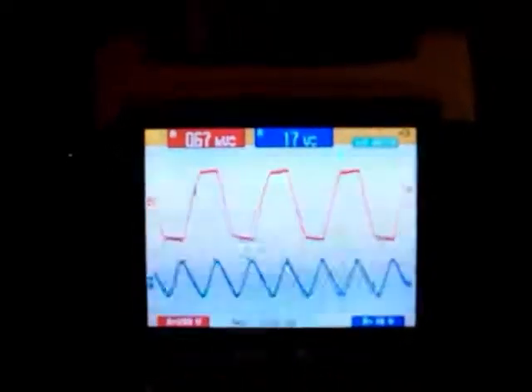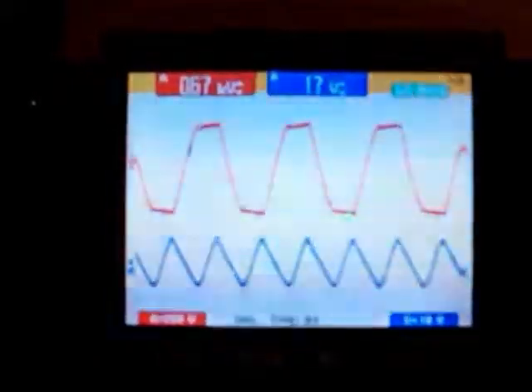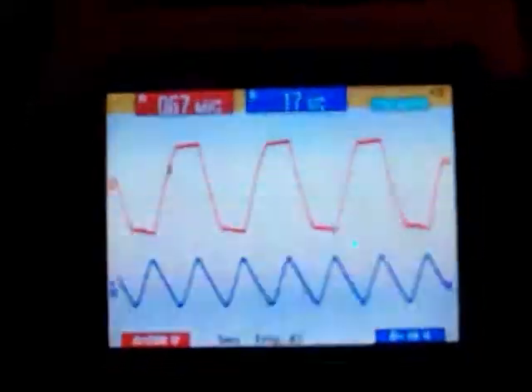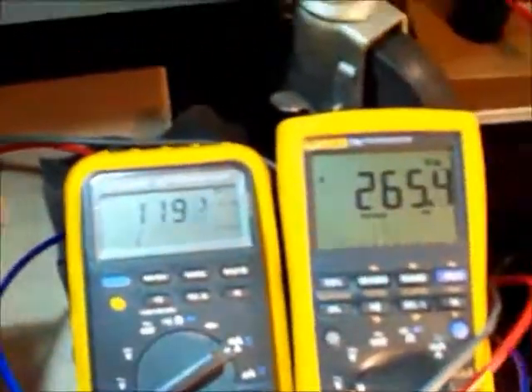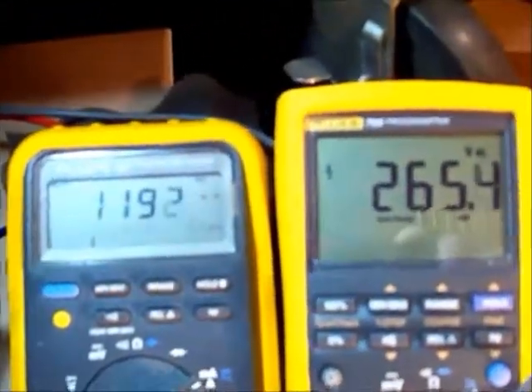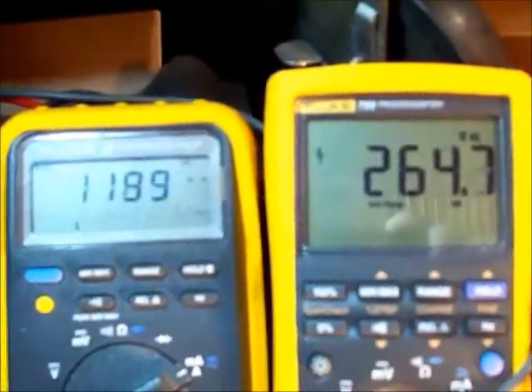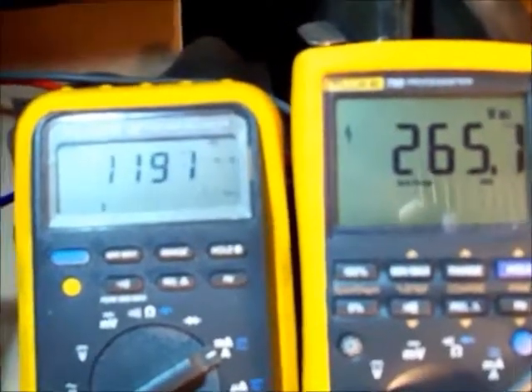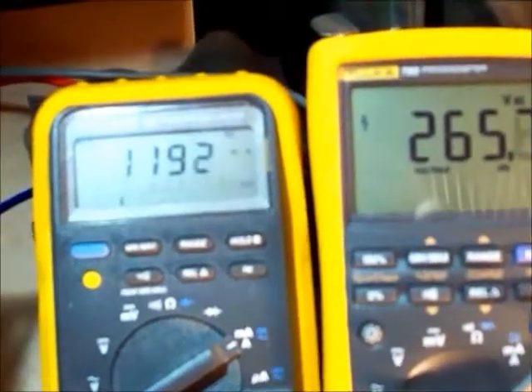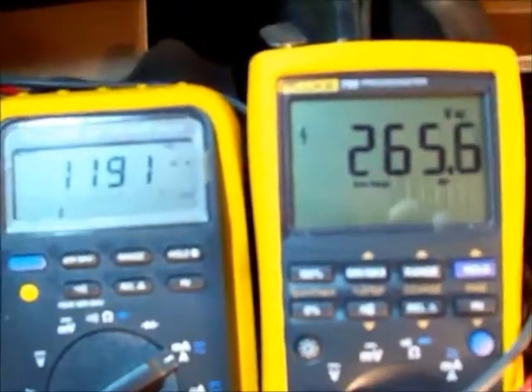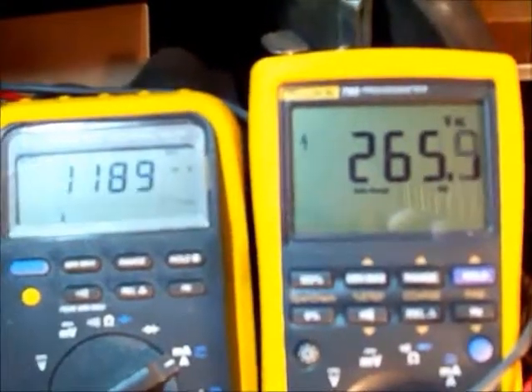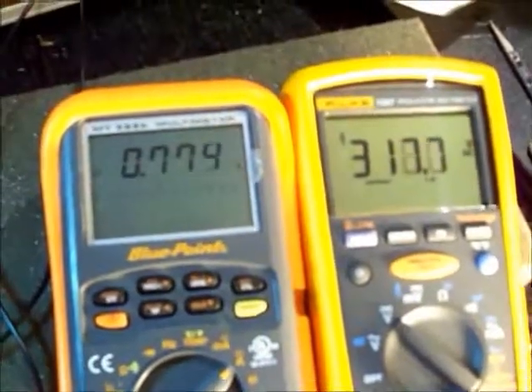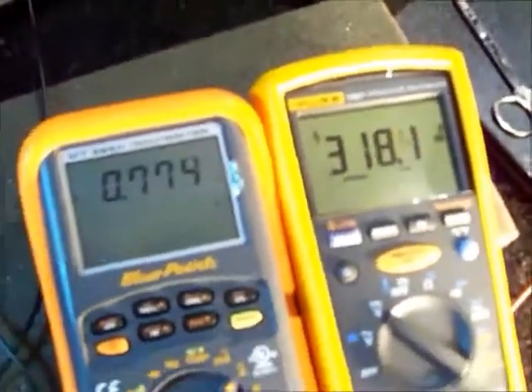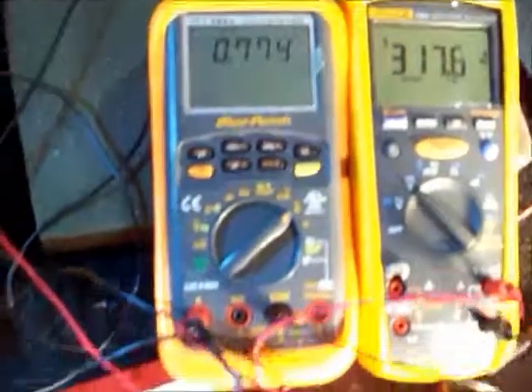Okay, we wanted to get one more shot of this. We put the caps back in, and you can see how it flattens out the circuit. It also has a big effect on current from the transformer. So with the caps back in, the transformer's drawing 1.1, almost 1.2 amps, and our voltage is 265 on the AC side. DC side is 775 and 317. So those are the numbers.